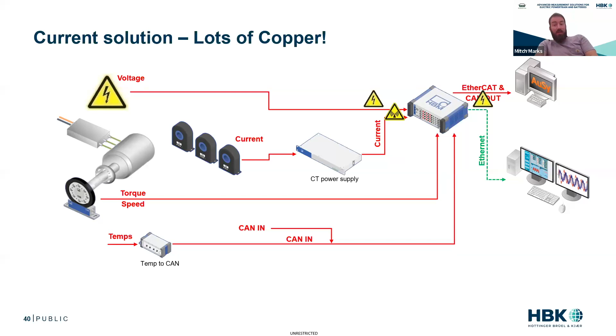So what if we made the measurement locally and then turned all those cables into fiber optic? HBK is coming out with what we call a fiber optic probe. It sits right next to the measurement, so your measurement cable could be maybe 10 or 20 centimeters. We digitize the measurement and bring it back fiber optically—no inductance, no capacitance, no possibility for conducted noise. You're really limiting that pickup to that 10, 20 centimeters. Short cables, low noise potential. Same with current: we're integrating the power supply into our fiber optic probe so we can amplify that current, digitize it, and send it back with no electrical noise potential. We're really minimizing that potential for electric noise.